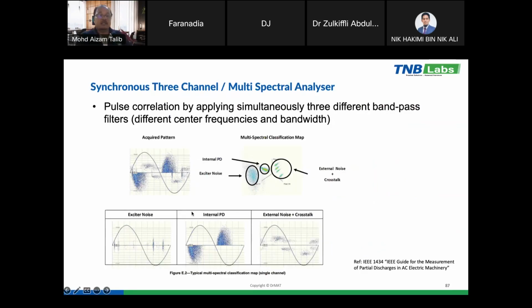And then the other advanced PD analysis we can use is the synchronized three-channel or multispectral analyzer, where we plot three signals at different frequency or at different phase. Okay, we have a phase resolved PD pattern. We plot at different frequency or different phase. Then we get certain clusters, and then we transform again to the phase resolved PD pattern. So through this three-channel or multispectral analyzer, we are able to differentiate between the noise, internal PD, or external noise plus crosstalk.